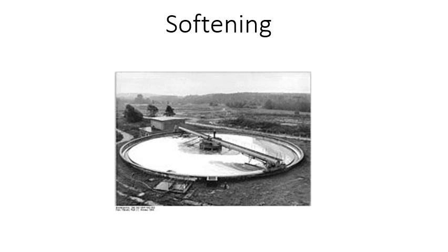Split treatment for water that's high in magnesium. About 80% of the source water is treated with an excess lime dose to raise the pH over 11.3. The rest, the 20%, is bypassed to the next tank to lower the pH of the excess lime treated portion. If permanent hardness is still present, the second stage adds soda ash to treat non-carbonate hardness. Split treatment can eliminate or reduce the need for recarbonation and purchasing CO2. Split treatment can reduce overall costs.